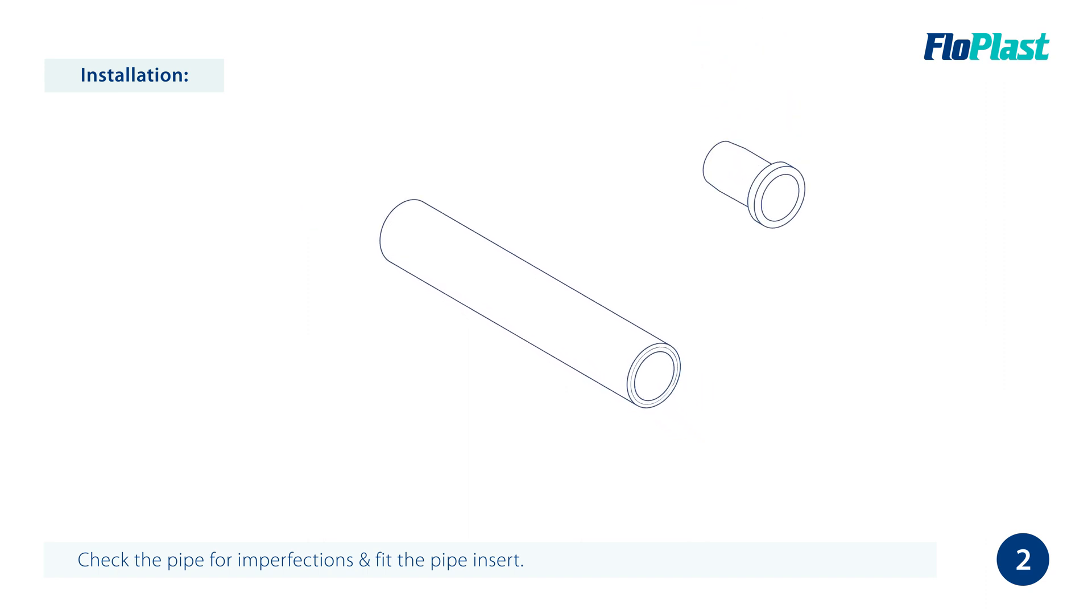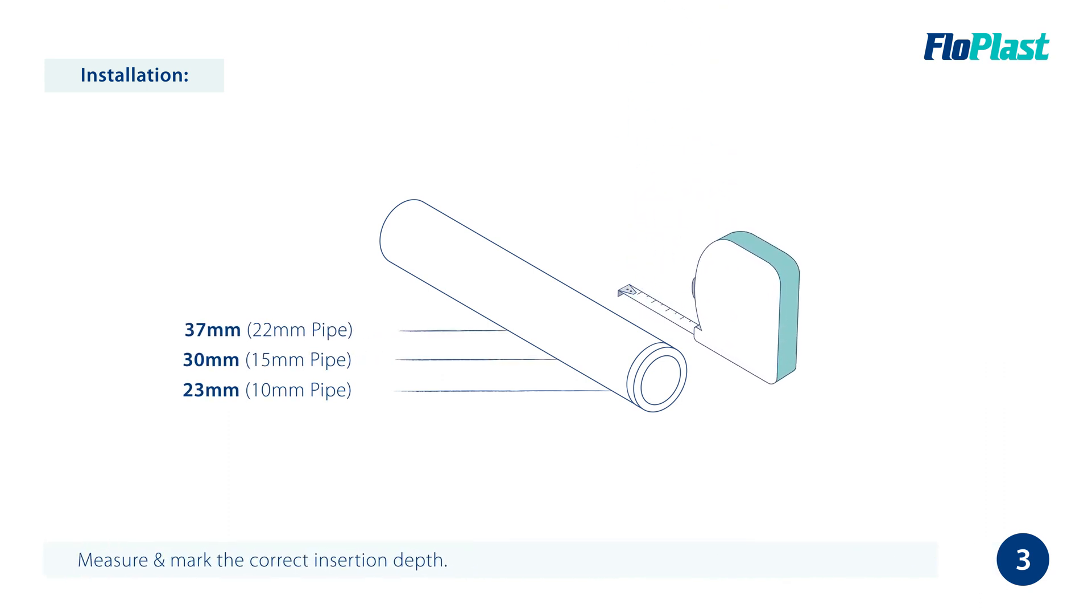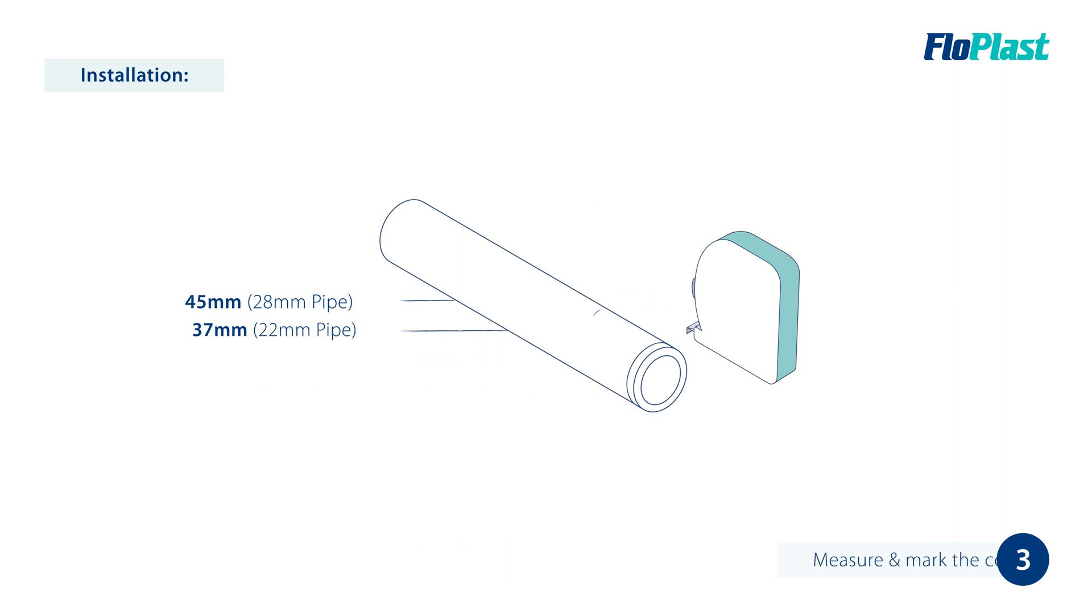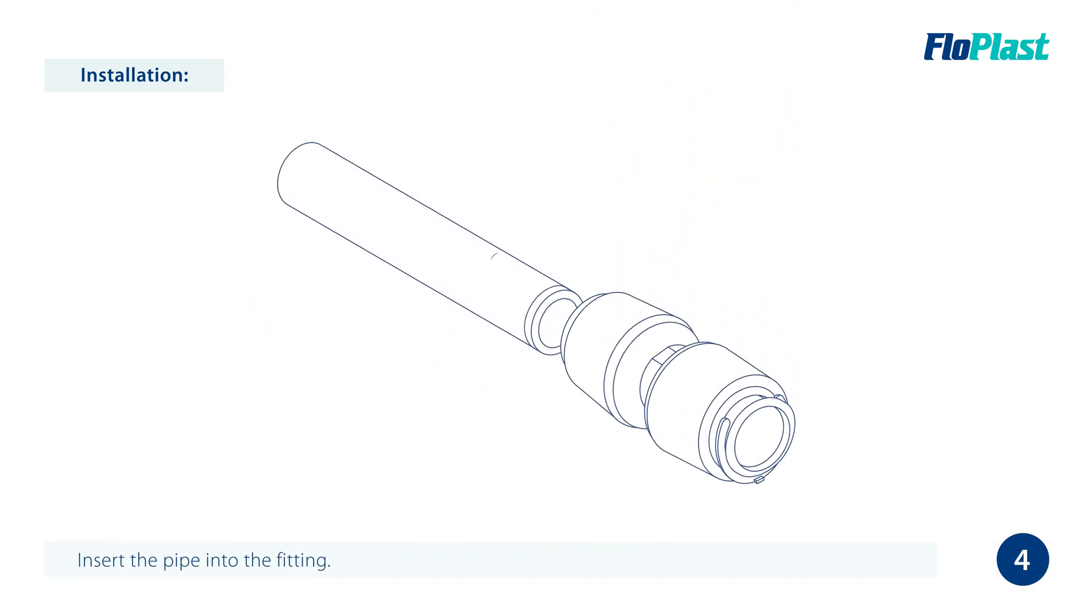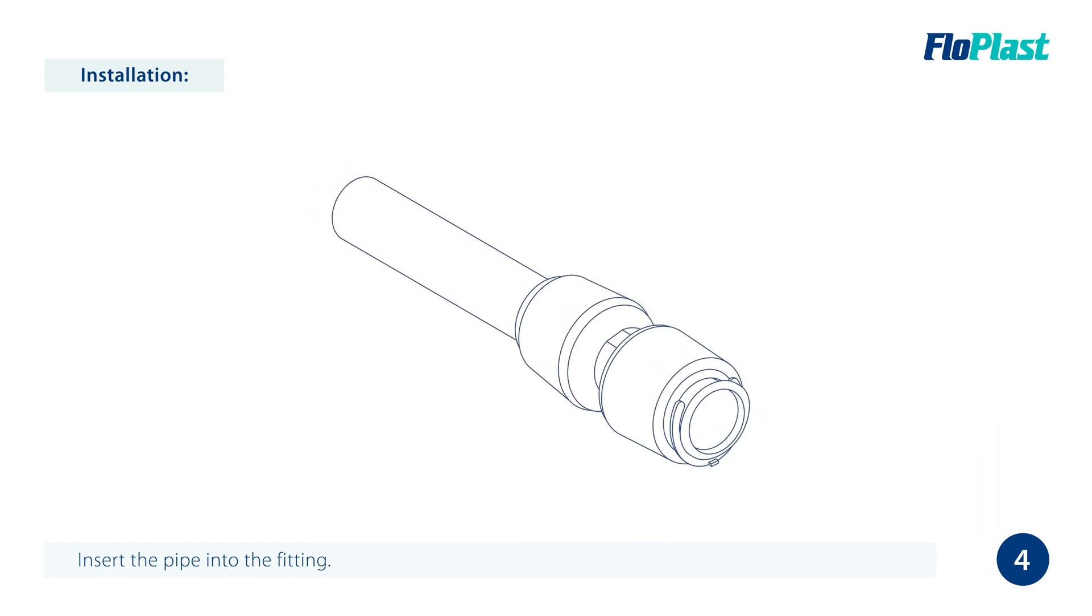Fit the pipe insert into the pipe ensuring it is fully inserted. Next, measure and mark the correct insertion depth on the pipe. Insert the pipe into the fitting ensuring it passes through the o-ring until it reaches the stop point and correct insertion depth. Check the assembly is secure by pulling the pipe away from the fitting.